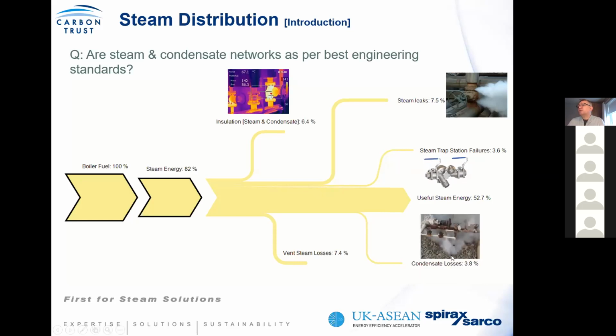You also look at condensate losses. So simple things like allowing condensate to go to drain. You can see in this scenario here, this is a case example where we're experiencing what we call stall. So in other words, the customer had traps that weren't working because of stall in the heat exchanger. The only way he could get the system to operate was to open a manual bleed valve. However, when you open a manual bleed valve, you can't account for different process conditions. And what we found here was that at times it was just pure steam coming out of it. And as the process load increased, then you got a lot more condensate. But again, the system here was operating like this because of what we call stall. So in other words, you put in the pump trap to compensate.